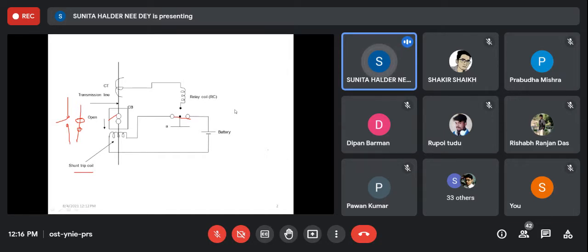But when the relay coil is energized, it closes a secondary circuit which energizes the trip coil. So this trip coil circuit is a low power circuit. Okay, the relay is also a low power circuit, but in the relay, the relay coil is energized to give the signal to the circuit breaker that you should open, and the trip coil will serve the purpose. The trip coil will initiate the circuit breaker to open and close the circuit when the trip coil is energized. Then this contact will move towards the trip coil and the circuit breaker will open. So in a circuit breaker, actually there are two contacts. One is a moving contact and one is a fixed contact. The fixed contact does not move. Only the moving contact moves for closing or opening.